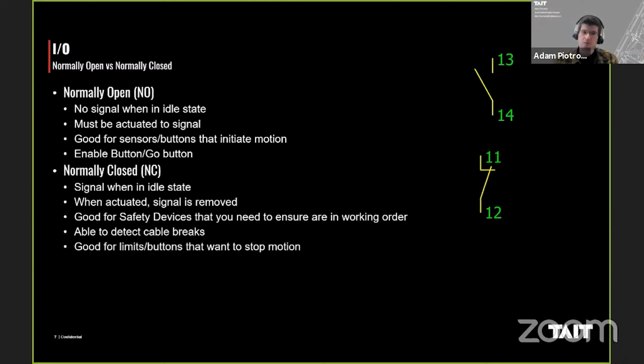This is good for limits and buttons that you want to stop motion, so that if the cable was to break, or somebody was to run it over with a forklift, or it's on a moving lift and gets severed by a shear edge, if that limit goes away, the control system is absolutely going to want to stop, because if the machine extends past its normal motion envelope and that limit doesn't exist anymore, you have no way of stopping it.